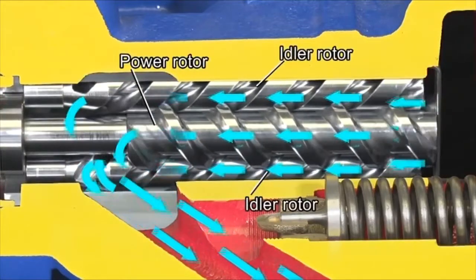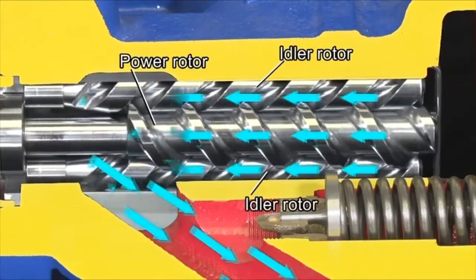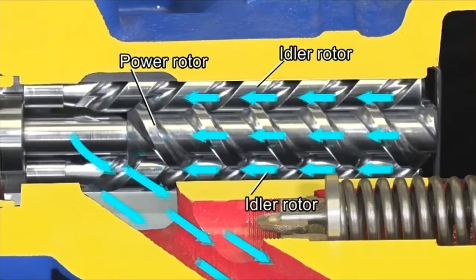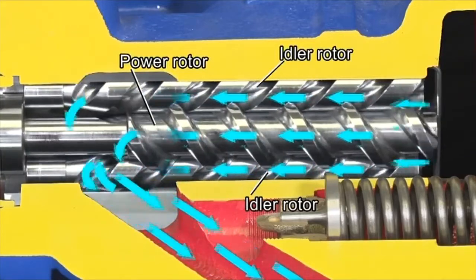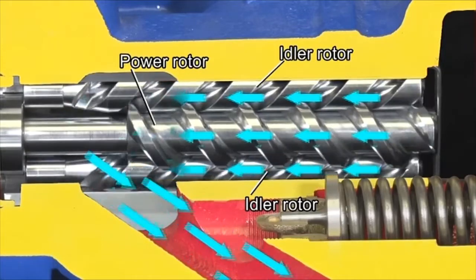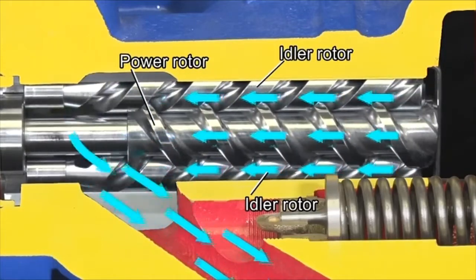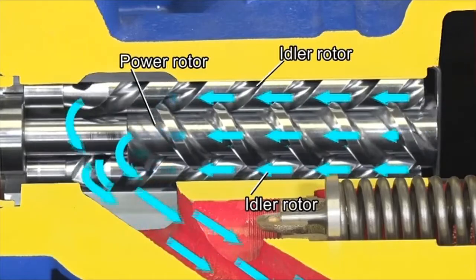When the power rotor is turned clockwise as seen from the drive side, the idler rotors turn in the opposite direction. This creates a sealed space per screw lead. It moves toward the discharge side along the screw shaft.